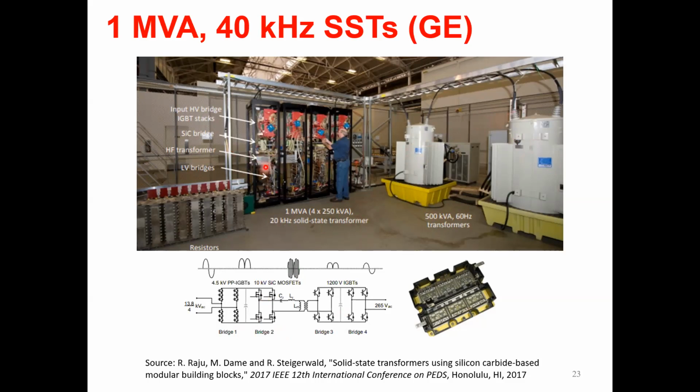I hope you are able to follow my cursor. So the transformers themselves for 250 kVA are so tiny, but there is an obvious issue. Again, this relates to what is practically possible, right? So here, of course, in terms of weight, definitely the solid state transformer will be lighter, as you can just guess from the figures. But in terms of volume, I don't see a big difference, right?